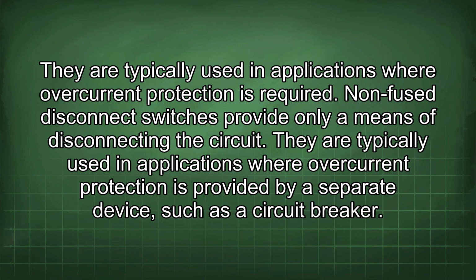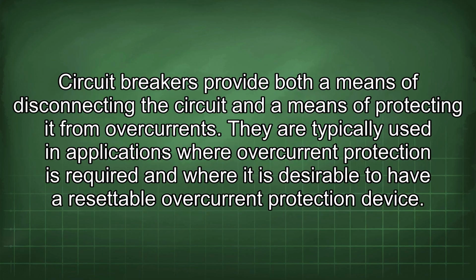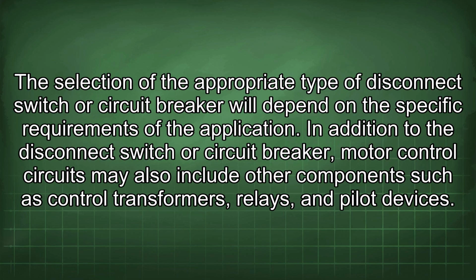Non-fused disconnect switches provide only a means of disconnecting the circuit. They are typically used in applications where overcurrent protection is provided by a separate device, such as a circuit breaker. Circuit breakers provide both a means of disconnecting the circuit and a means of protecting it from overcurrents. They are typically used in applications where overcurrent protection is required and where it is desirable to have a resettable overcurrent protection device.